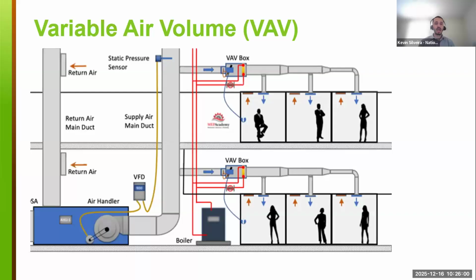Next, we have the most complex system out there, the variable air volume system. This system is really for newer and larger buildings, might not be in any of your municipalities, might be in some of them. Really, only buildings built around the 2000s would have this system. Basically, you have an air handler that is providing either cooled air or neutral air to VAV boxes. In the summer, they're just varying how much cold air goes to the space, or in the winter, it's bringing in neutral outside air, and the VAV box is doing all the heating. Those VAV boxes can be hydronically fed or electric resistance, and you can have simultaneous heating and cooling in a building in this configuration.